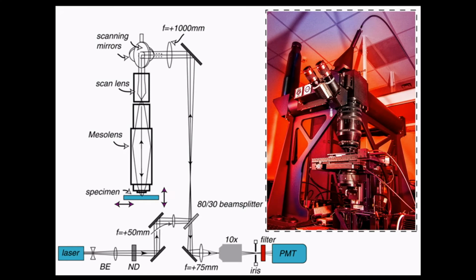So when we conceived of the Mesolens, that 6mm field of view and 3mm working distance was not an accident. We'd spoken extensively to the Mouse Atlas community, and we had envisaged that they would be one of the main users of the technology. And a mouse embryo, when it's day 12 and a half, is exactly 6mm long, and it's about 2.5mm thick. So that's how we arrived at the design specification, and then with the resolution we wanted to see inside every cell of that type of specimen.